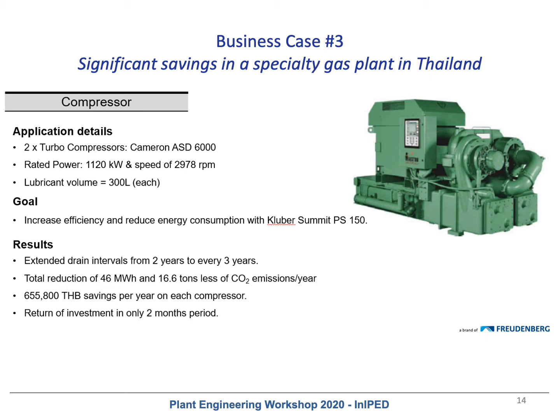2,978 RPM. The sump size for the lubricant volume was quite large, with every compressor containing just a little bit over 300 liters. The goal was increasing efficiency and reducing energy consumption by using the Kluber Summit PS 150. The result was an extended drain interval from every 2 years to every 3 years. The total reduction was 46 megawatt hours and a reduction of CO2 emission of 16.6 tons per year. In local currency, that represented over 650,000 THB saving per year on each compressor. The return on investment was only a 2 month period.